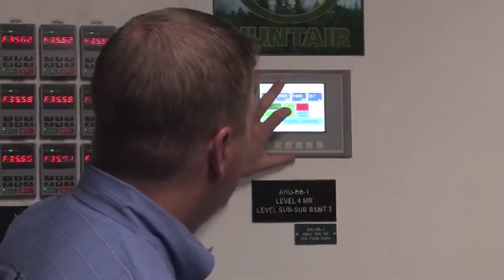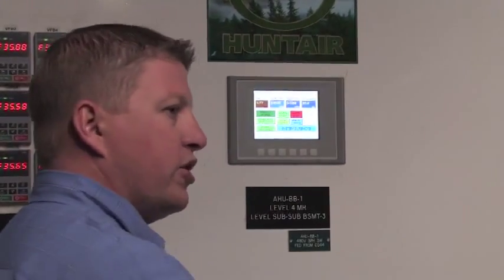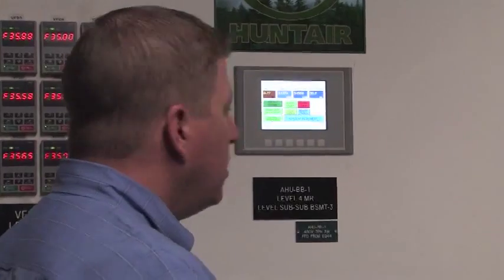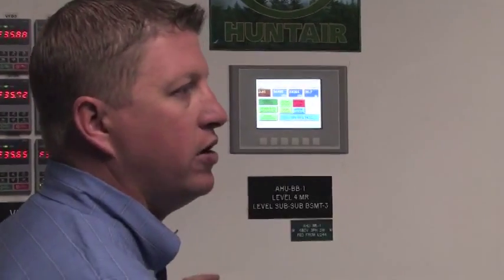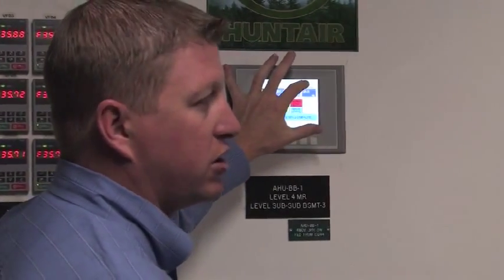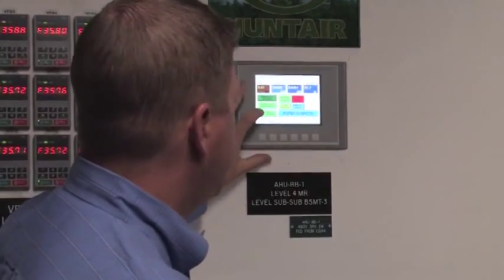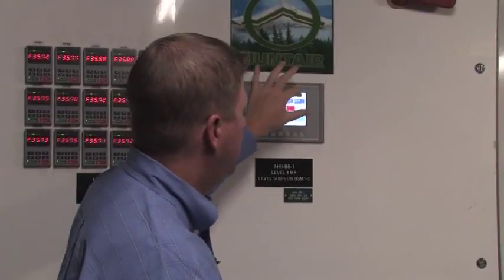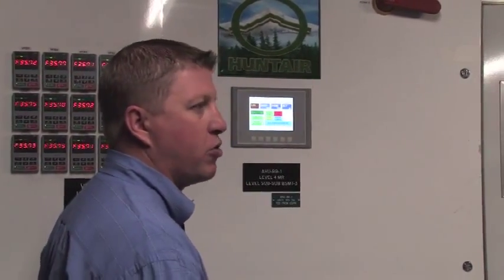If I wanted to take it into local control, I push local control. The unit will shut down just like a VFD. If you go from hand off auto, you go into local or hand. Local control is basically hand control. And then you can go in and set your CFM. You would enter the CFM you want. Or some people are more comfortable controlling the hertz. You can disable CFM control, which would allow it to be hertz, and then control to the speed of the drives, whichever way you're more comfortable.